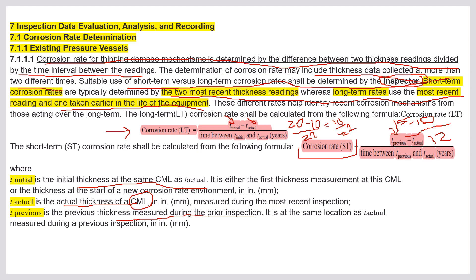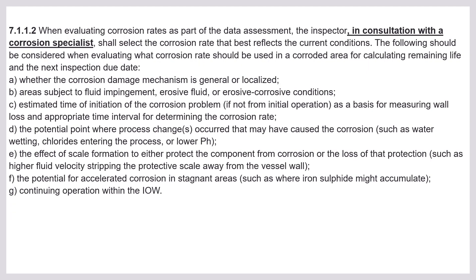When evaluating corrosion rate as part of the data assessment, the inspector in consultation with a corrosion specialist — this is a must question in the close-book exam — shall select the corrosion rate that best reflects the current condition. The following should be considered when evaluating which corrosion rate to use in a corroded area for calculating remaining life.